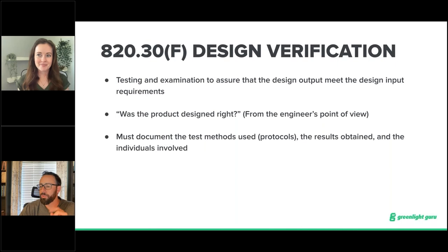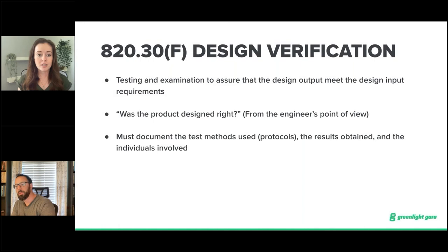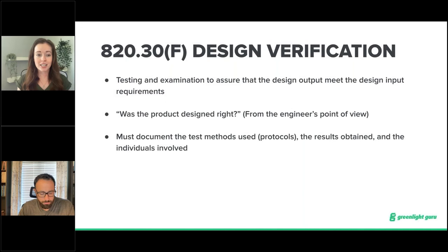Question: Can a non-responsible reviewer be an expert on the regulatory consulting firm being used for ISO 13485? Answer: As part of design reviews, you can bring in anyone you deem necessary. Design reviews are not limited to just the person responsible and an independent reviewer. Bringing in all key stakeholders or anyone with valuable insight is always recommended. If a non-responsible expert for MDR or ISO 13485 needs to come in, absolutely bring them in — it will only help by potentially identifying issues early on.